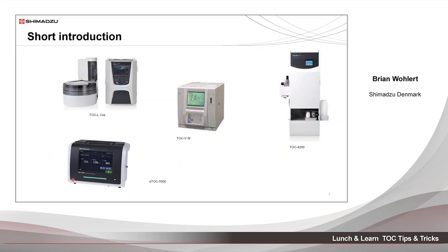The newest part we have is the ETOC 1000. This is an online TOC analyzer as well. And the oxidization principle of this instrument is done by UV oxidization. And the detector is a conductivity sensor. This is most suitable for highly purified water such as water for injection and purified water for the pharmaceutical industry or even for the semiconductor industry.